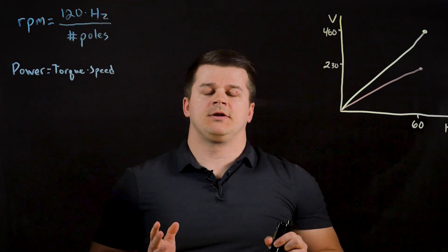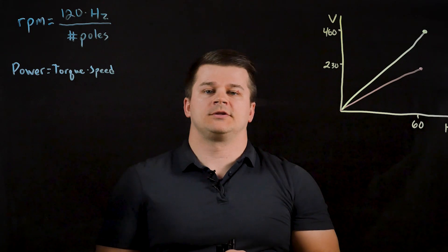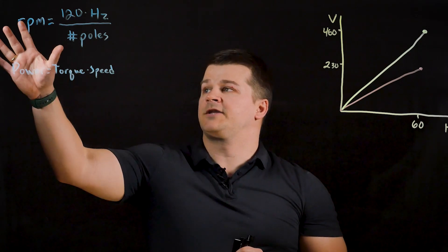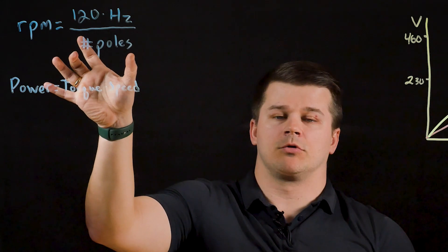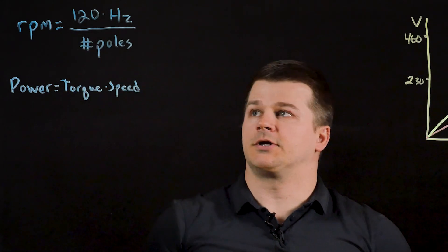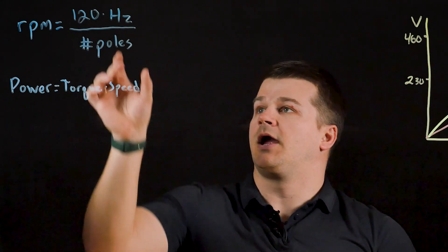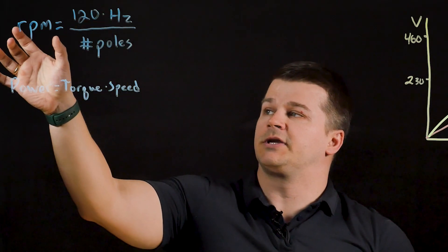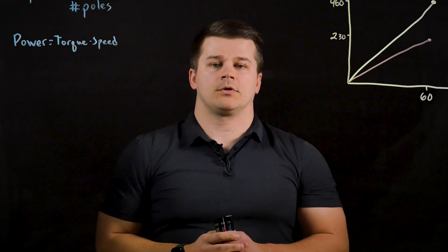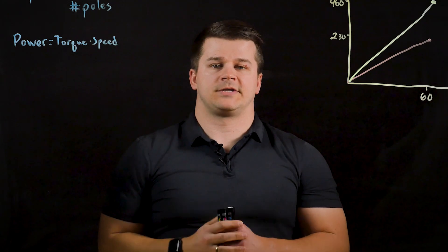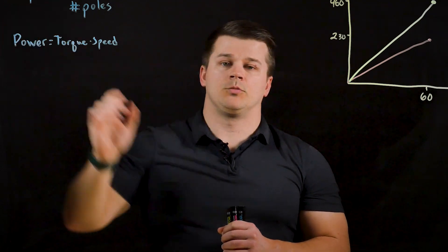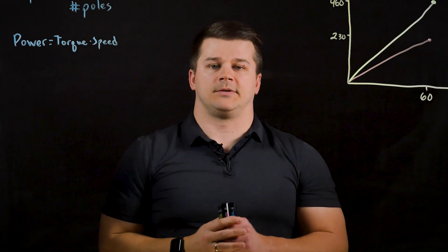The speed of the motor is directly proportional to the output frequency to the motor, based on this equation. The number of poles of the motor will be known, such as a four-pole induction motor, and then based on the output frequency we can calculate the RPM. For the standard four-pole induction motor running at the rated speed of 60 Hertz, this speed will be 1800 RPM minus the slip.